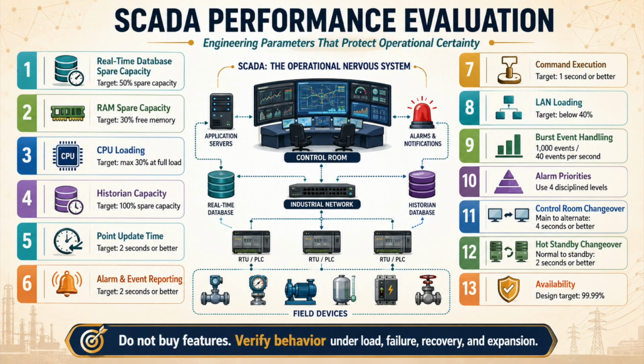Historian sizing must include write rate, query response, trend rendering, archive strategy, compression, backup, restore, retention, and recovery, not just disk volume, because storage without retrieval performance is not useful operational memory. The fifth engineering parameter is configurable SCADA point capacity, because 65,000 configurable points may be a practical baseline for medium and large systems, but point count without behavior is misleading.